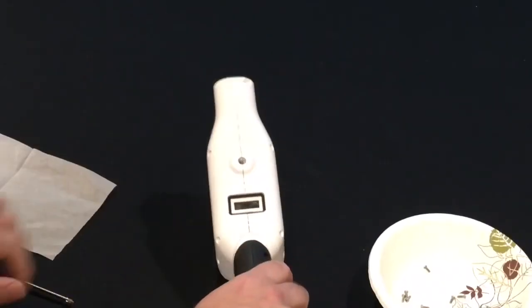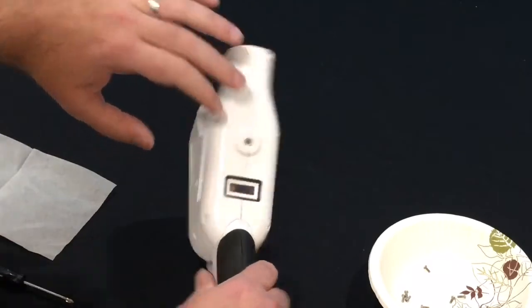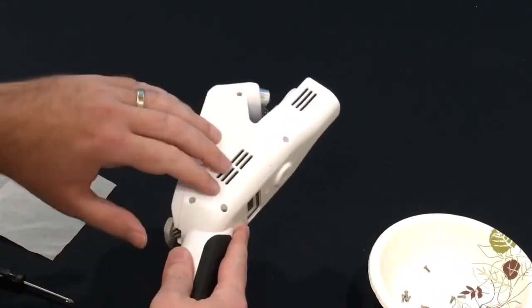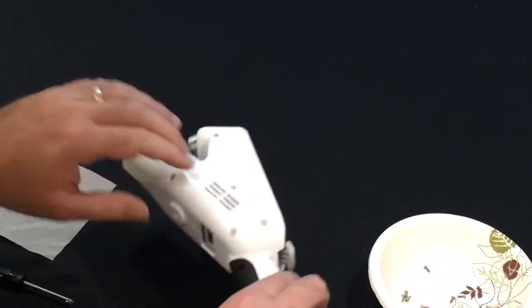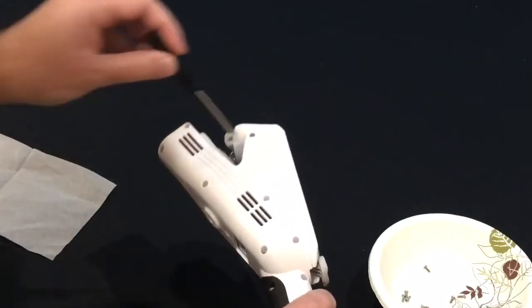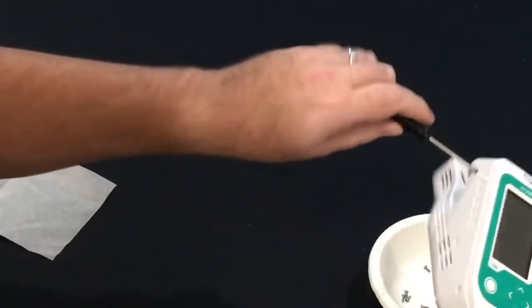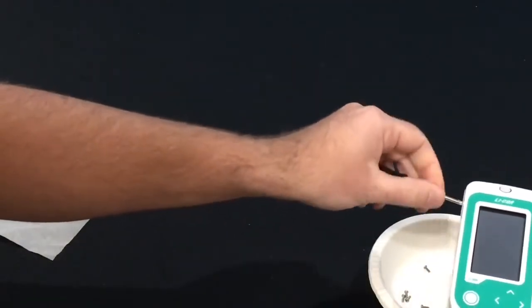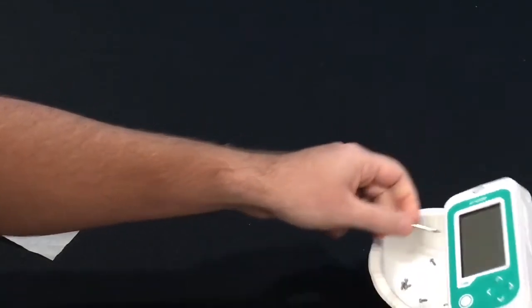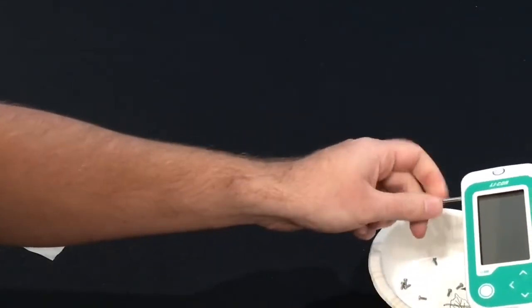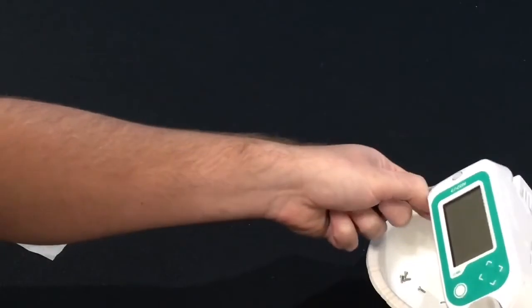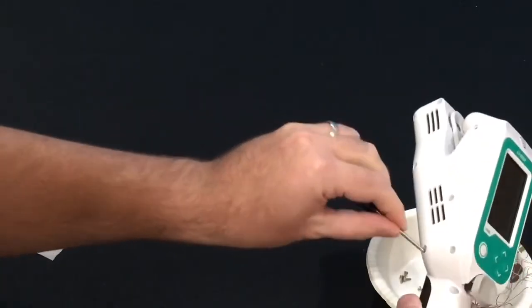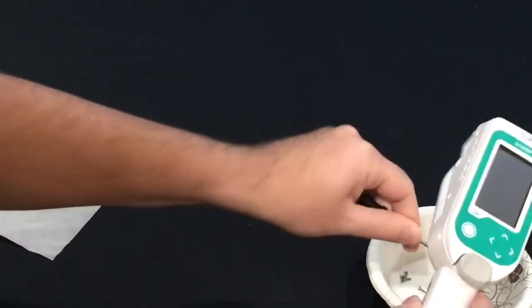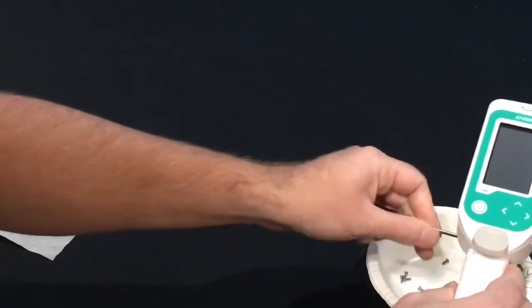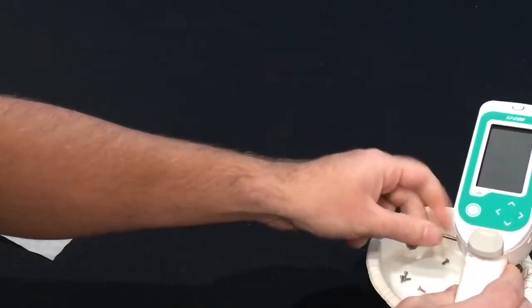First, we will start by taking the 2 shells off of the instrument. There are 5 screws on the right side and 7 screws on the left side. And really, all you need to do is remove those screws with your Phillips screwdriver and empty them into the bowl. These screws are all the same size, so you don't have to worry about keeping track of which one is which.